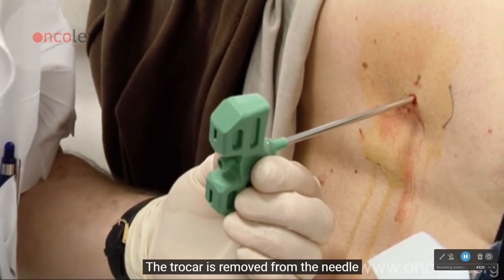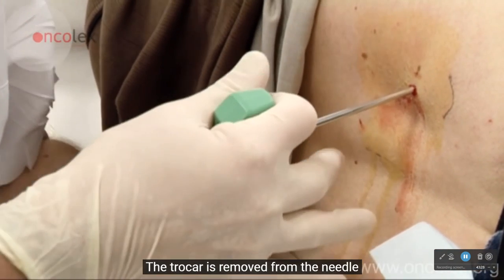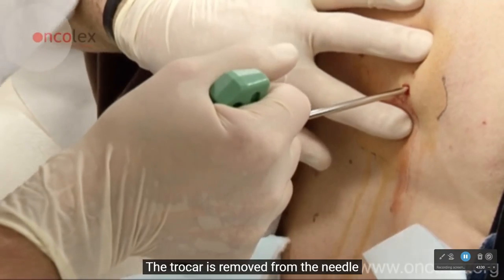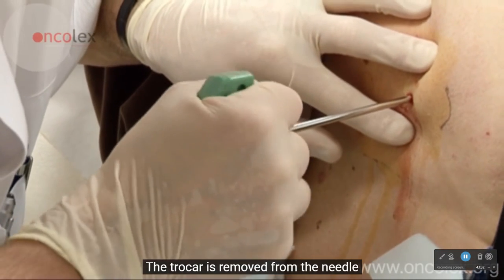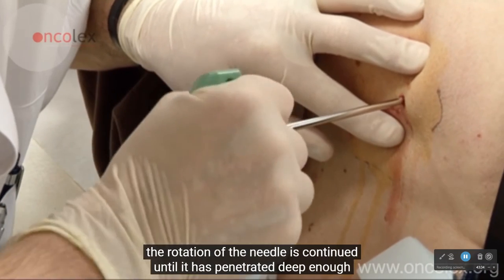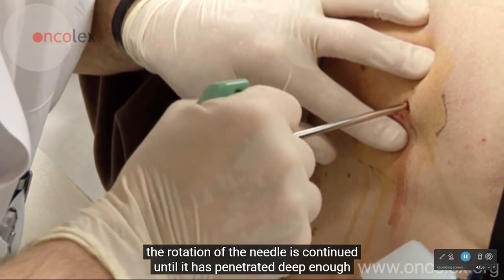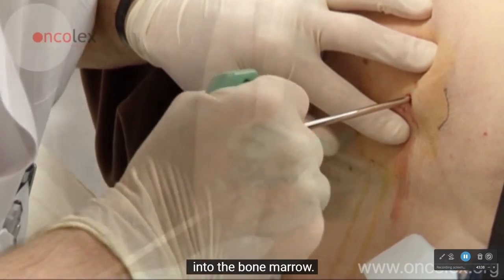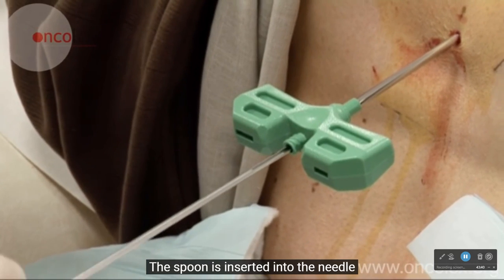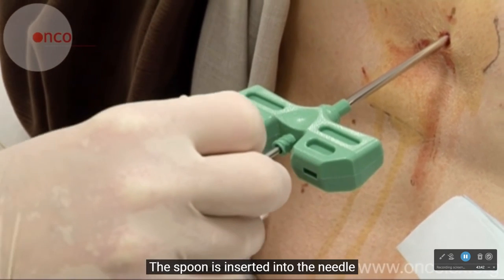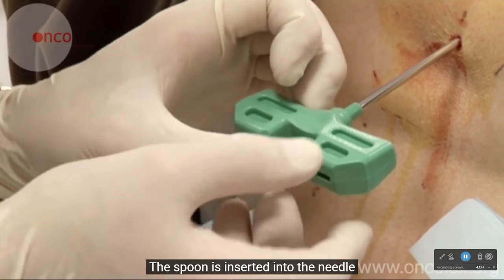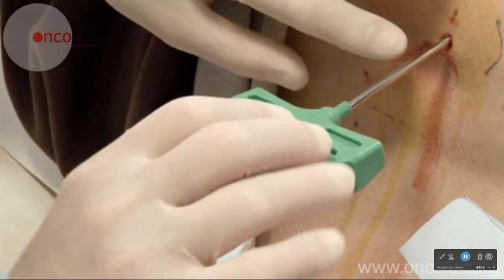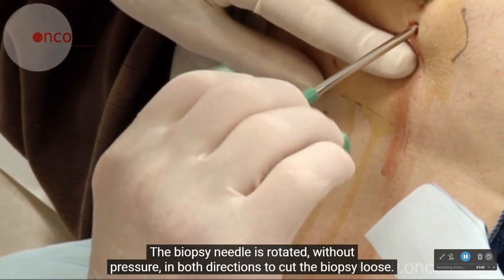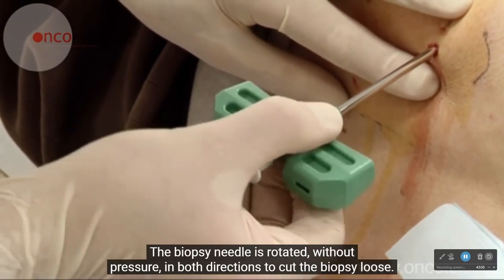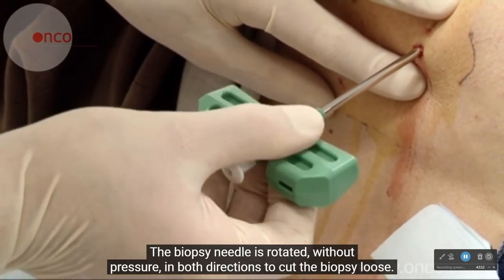The trocar is removed from the needle. The rotation of the needle is continued until it has penetrated deep enough into the bone marrow. The spoon is inserted into the needle. The biopsy needle is rotated without pressure in both directions to cut the biopsy loose.